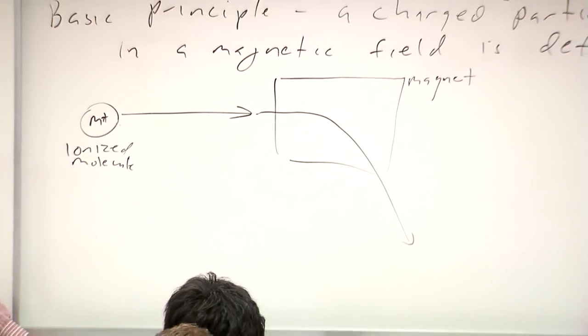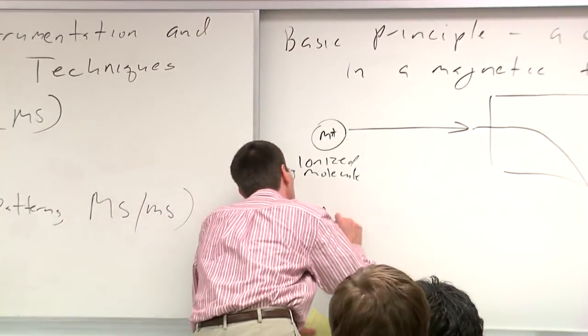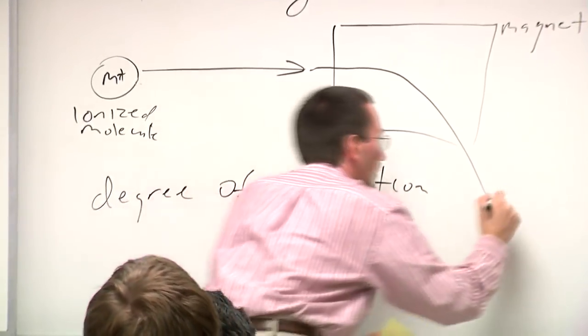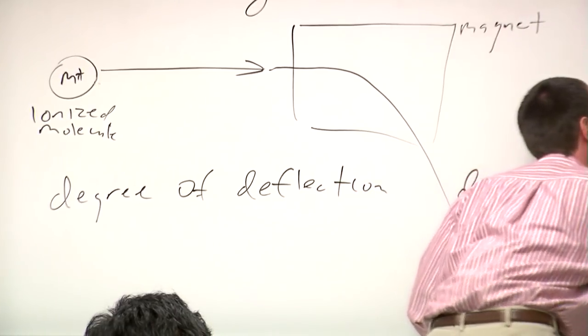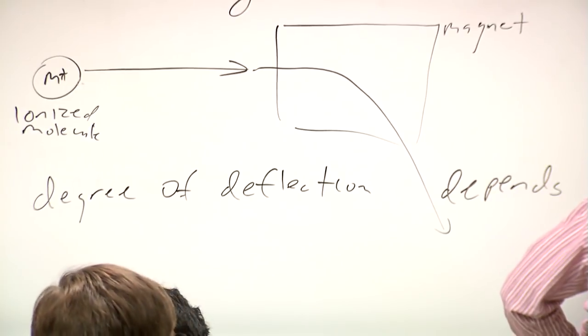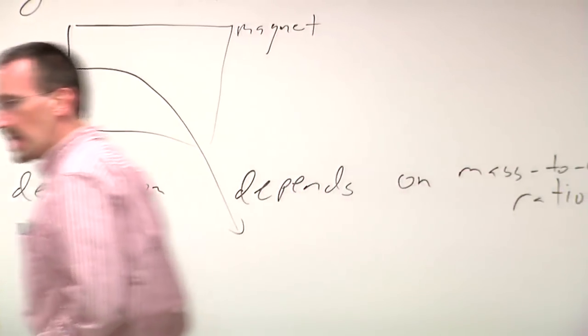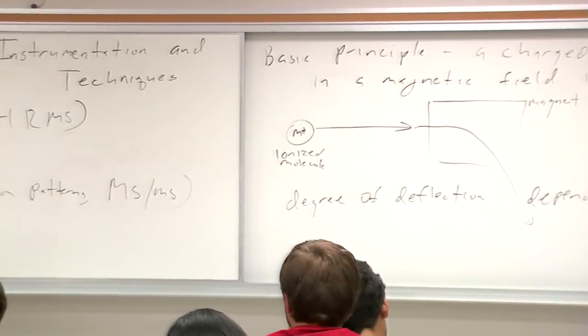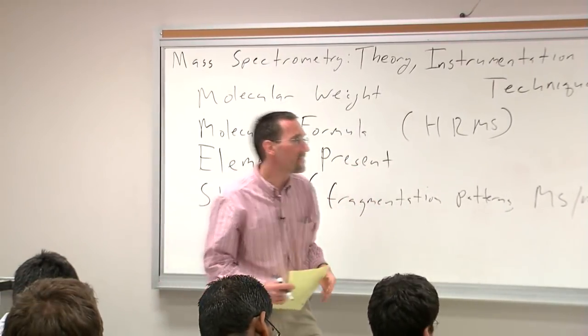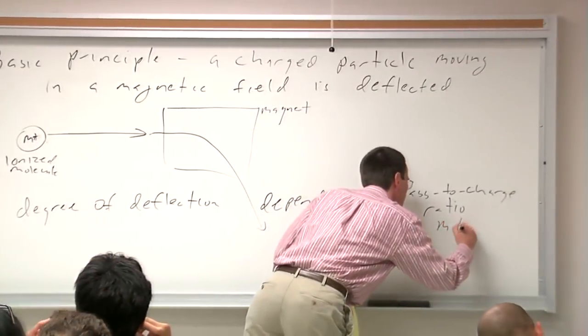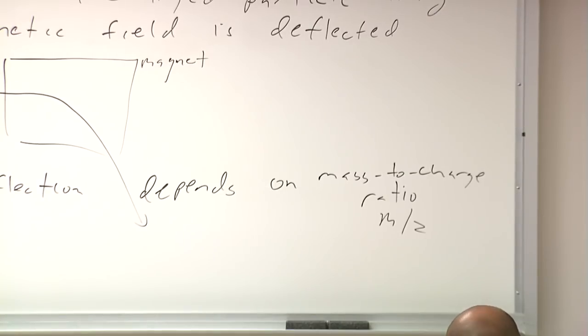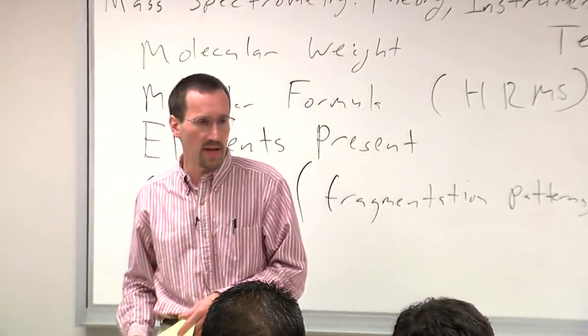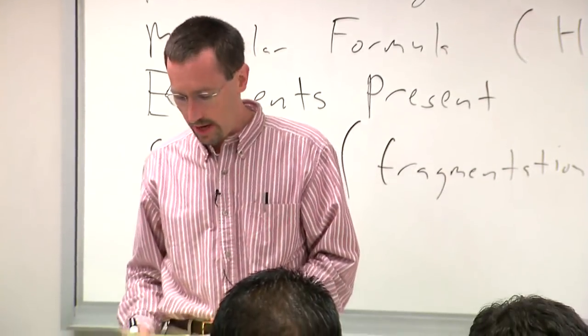The degree of deflection depends on the mass-to-charge ratio. Any given particle, whether it has 20 AMU and one charge or 40 AMU and two charges, is going to get deflected the same amount. So it's the mass-to-charge ratio you're seeing on the x-axis — not mass alone. This becomes particularly important when you're doing ESI, electrospray ionization mass spec, on reasonably big molecules where many times you get more than one charge on a molecule.